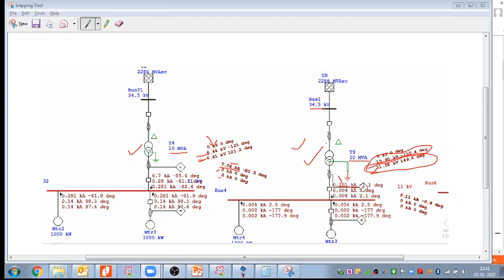Point number two: if you are not able to get this information from the vendor, then how much current can I put here? In that case, my allowable current, I can take at most my full load phase current. Because my full load phase current, suppose this is 400 ampere or 500 ampere, is flowing in the motor or the generator, and the core is not getting damaged. It means the core can withstand this much current. So for my NGR I will take the current equal to the full load current of the motor or the generator.